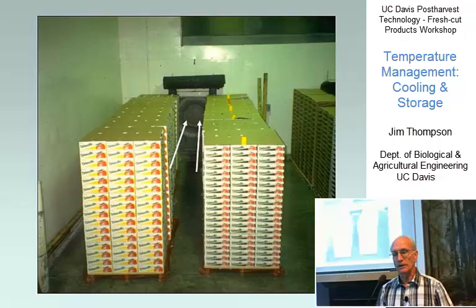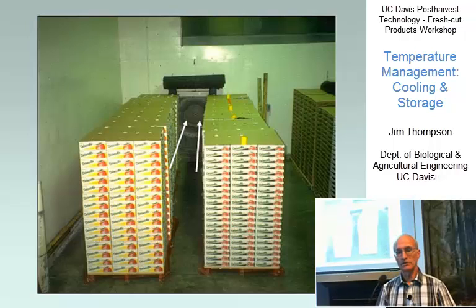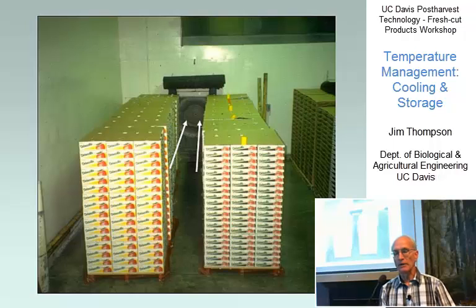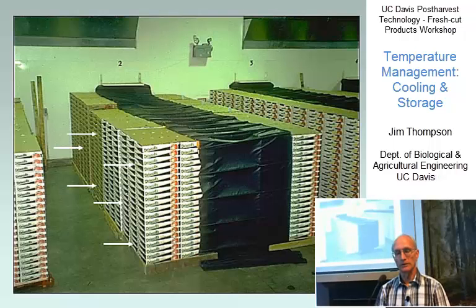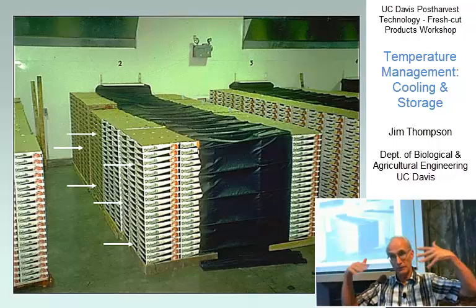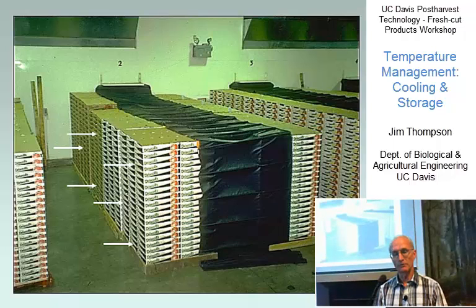Here you can see a picture with strawberries — the fan is in the back. The tarp is black and hasn't been unfurled yet, but it will be rolled out to cover that open area, and the air will flow through the berries and return to the fan, be recooled, and recirculated in the room. In this picture with the tarp in place and the fan on, you'll notice how the black tarp is sucked down because of the negative pressure in that return column.